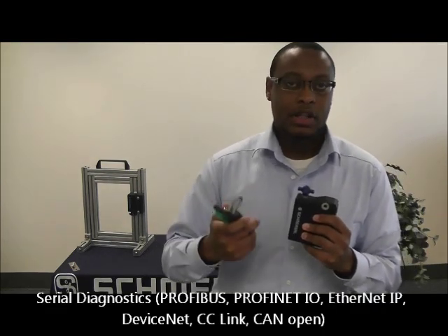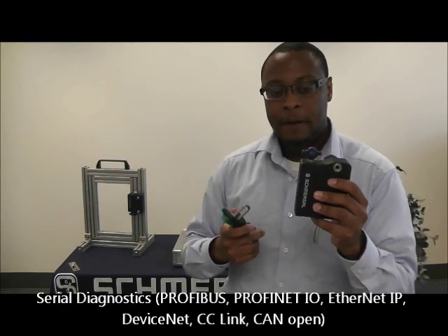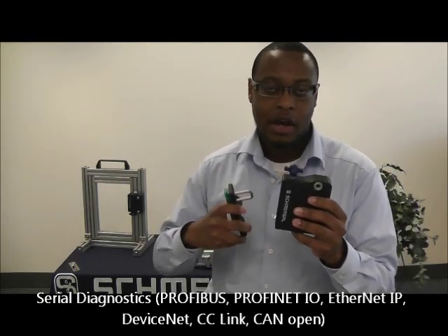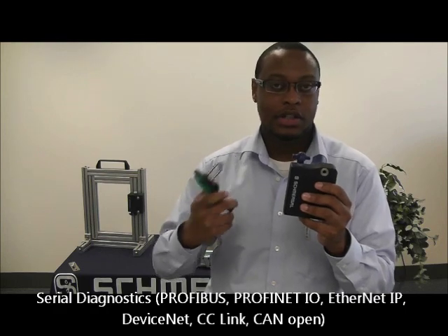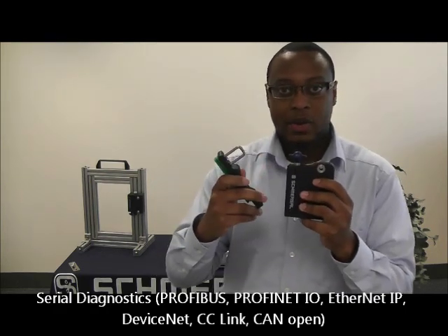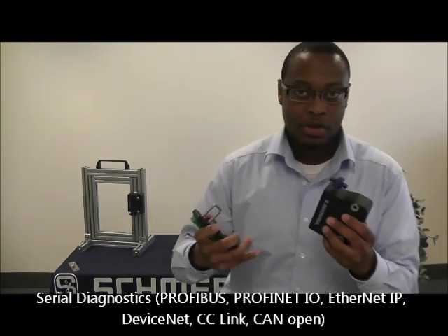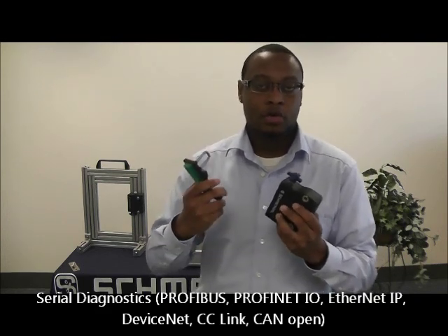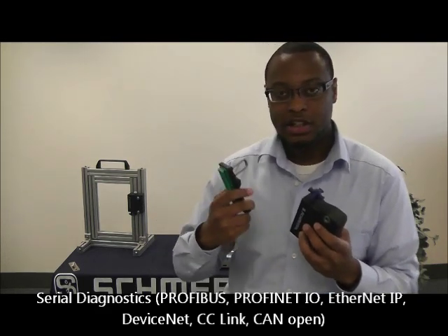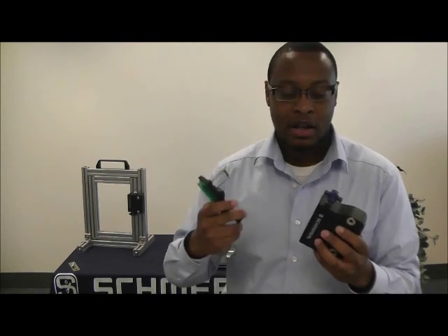We also have, for both the AZM300 and the AZM300B, we have the standard diagnostics, which is the 24 volt signal saying that the door is open or closed, and we also have the option for serial diagnostics, and that will give you more detailed information about the status of the AZM300, such as if the temperature is too high, if you have any faults on your safety outputs, if there's damage to the actuator, if there is an incorrect position with your rotary handle. Numerous errors can be relayed over a network using different protocols, such as Ethernet IP, Profibus, DeviceNet, just to name a few.